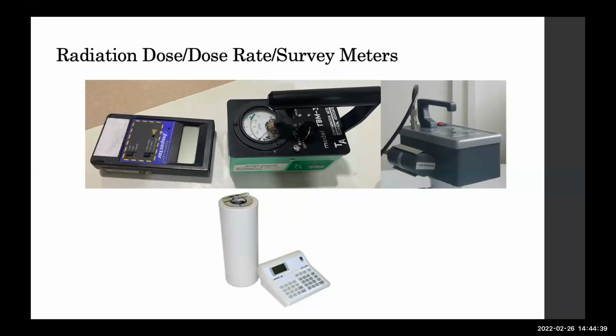If we are administering a particular radiopharmaceutical, it should be measured and it should be given for that particular scan or particular individual based on his age and weight. That radiopharmaceutical should be measured in the dose calibrator before injecting into the patient. And there are various formulas, even a pediatric formula. If a pediatric patient is there, how much dose that particular baby we have to administer, and that administered dose has to be measured here before injecting into the patient.